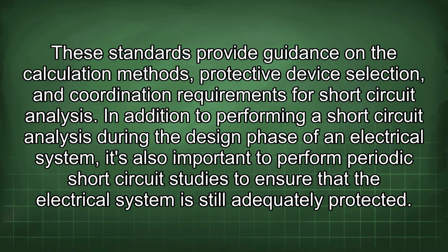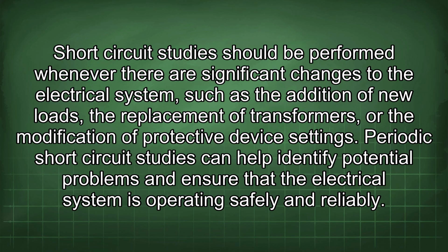In addition to performing a short-circuit analysis during the design phase of an electrical system, it's also important to perform periodic short-circuit studies to ensure that the electrical system is still adequately protected. Short-circuit studies should be performed whenever there are significant changes to the electrical system, such as the addition of new loads, the replacement of transformers, or the modification of protective device settings. Periodic short-circuit studies can help identify potential problems and ensure that the electrical system is operating safely and reliably.